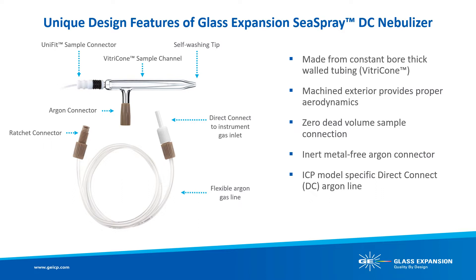Now let's take a closer look at the unique design features of Glass Expansion's Sea Spray nebulizer. All glass concentric nebulizers from Glass Expansion feature our unique Vitricone sample capillary, which is entirely different from competitors that use a hand-drawn glass sample capillary. The Vitricone is machined from a thick-walled glass capillary, providing highly reproducible geometry and constant internal diameter from sample inlet to tip, resulting in the highest manufacturing tolerances and ensuring consistent analytical performance from one nebulizer to the next.